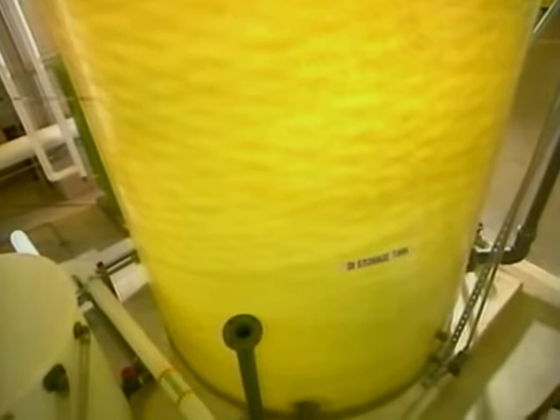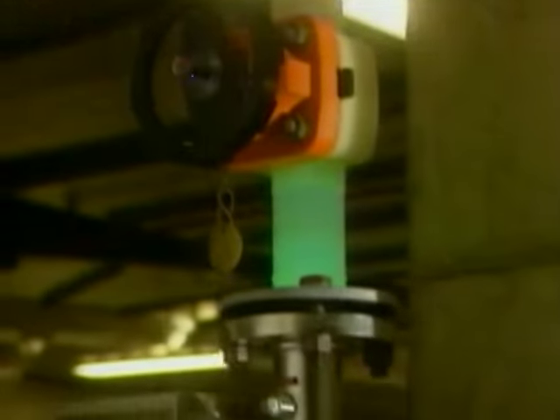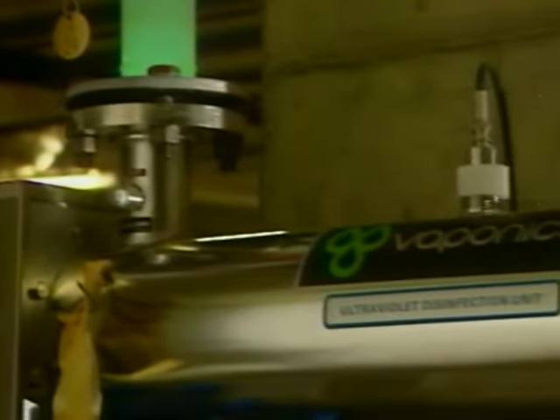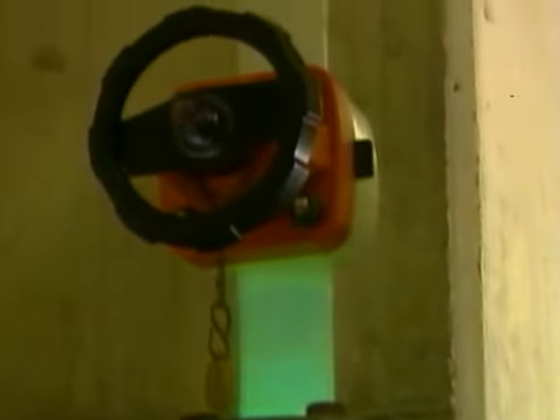Another critical mechanical system in Archives 2 is a deionized water system whereby water passes through reverse osmosis filters as well as through ultraviolet lights to eliminate all bacteria in order to provide deionized water to the labs via a central system. That water is used in the laboratories for a variety of conservation techniques.